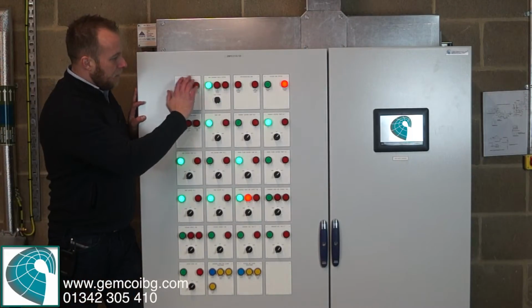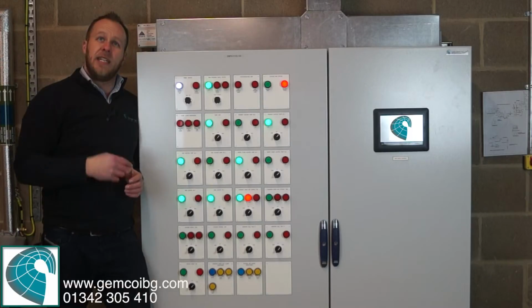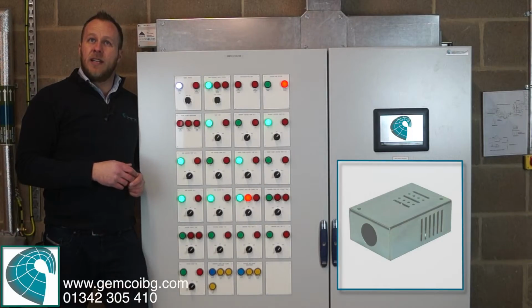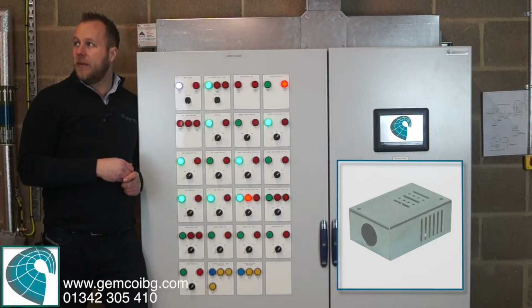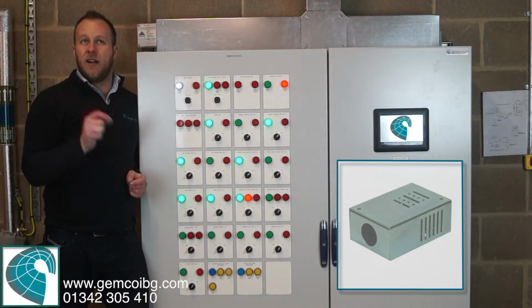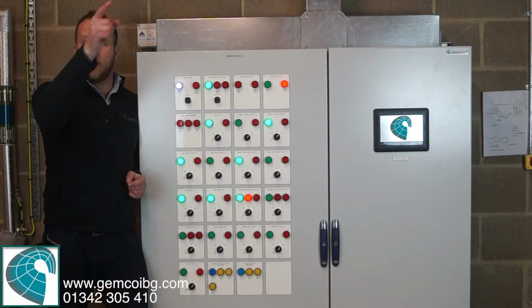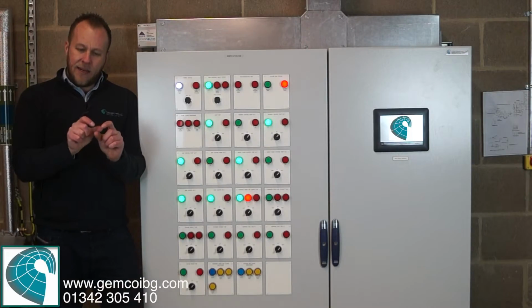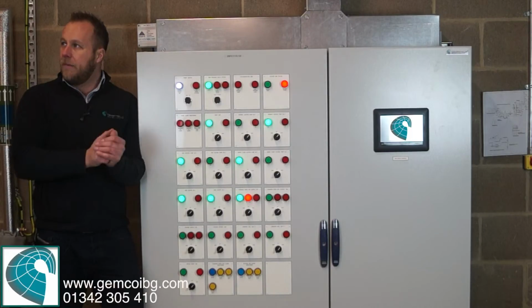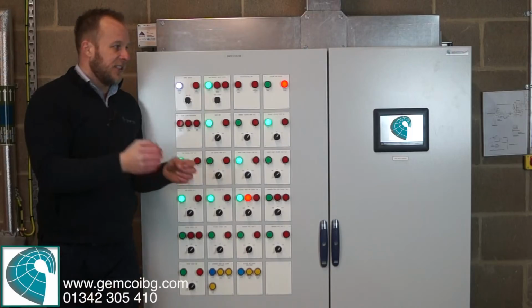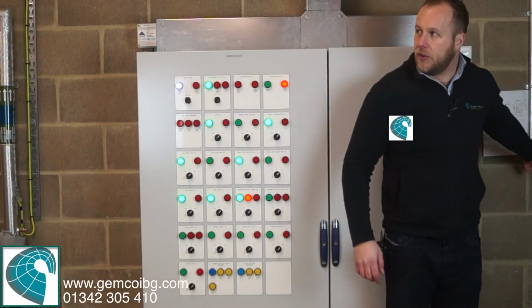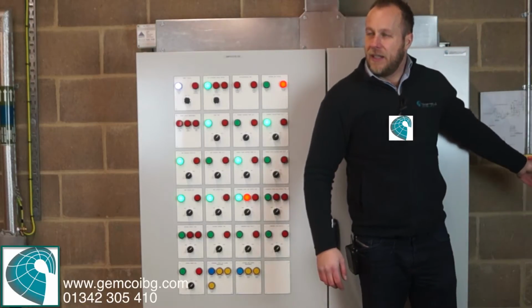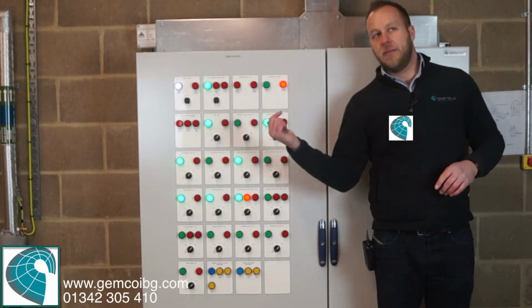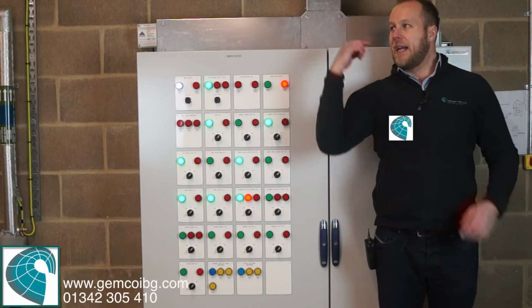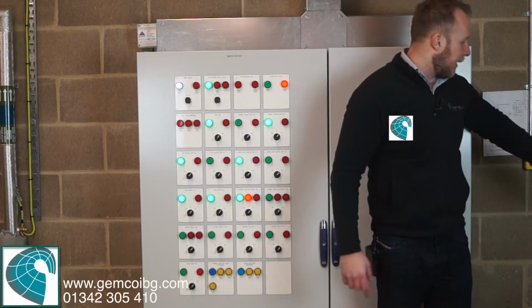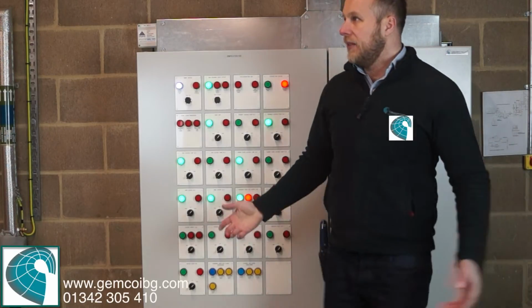And then above the hot water heaters up there, you'll see thermal links. So those big orange and blue heaters, there's a little grey box floating above it with a bit of tube coming off of it. Okay, that's a fusible link. Any gas appliance like that, or the GHP, you've got a bit of lead in there which will melt under fire. So if there's a fire, it will heat up and it will melt the link. And that circuit is wired in with the knockoff button by the door as well. There's a red knockoff button. Okay. And that's one circuit. So that circuit comes out of the panel, goes to that, goes to that, goes to that, and then back and says I'm healthy. And if any of those rupture, if you break that or those melt, then you're going to shut down the gas.